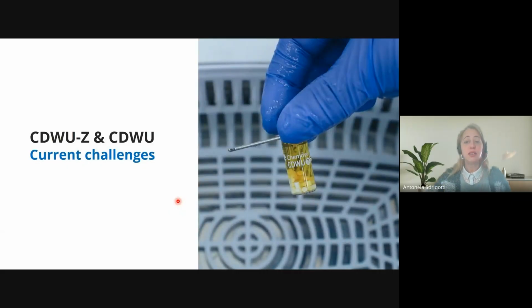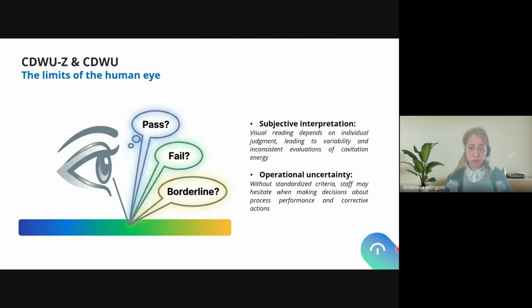But what are the current challenges of the interpretation of these indicators, regardless of being the U or the Z? First of all, and the most obvious one, the limits of the human eye. The subjective interpretation of the visual reading makes a dependence on individual judgment, leading to variability and inconsistent evaluations of cavitation energy. And of course, as a consequence, we have operational uncertainty. Without standardized criteria, staff may hesitate when making decisions about process performance and corrective actions.